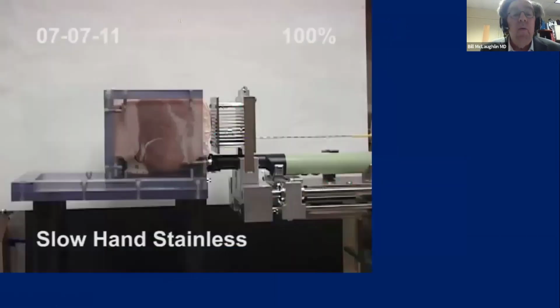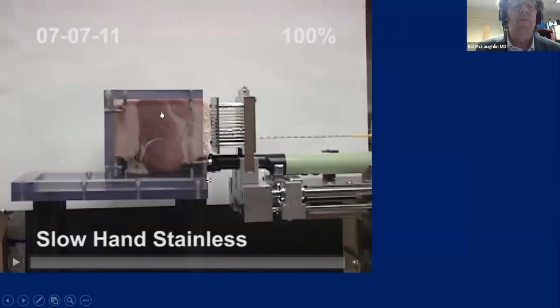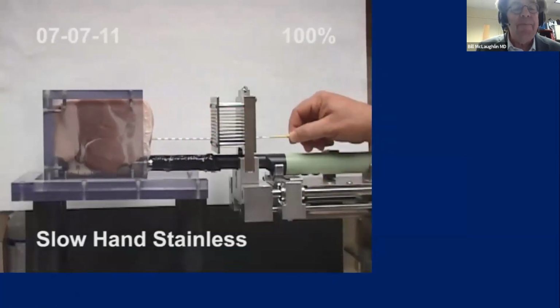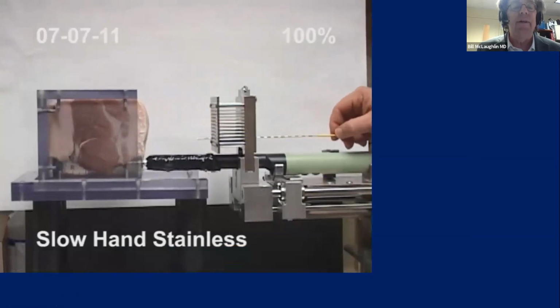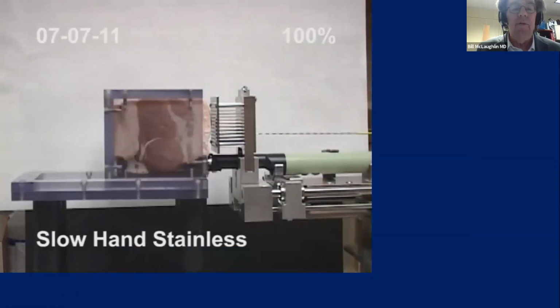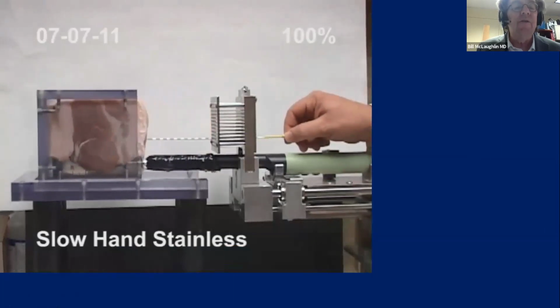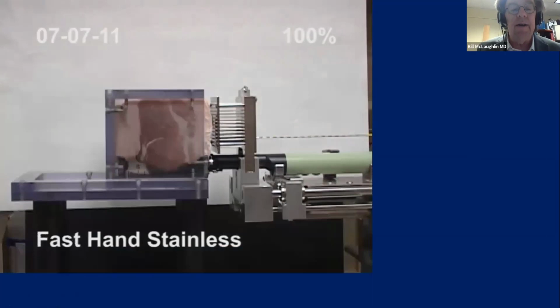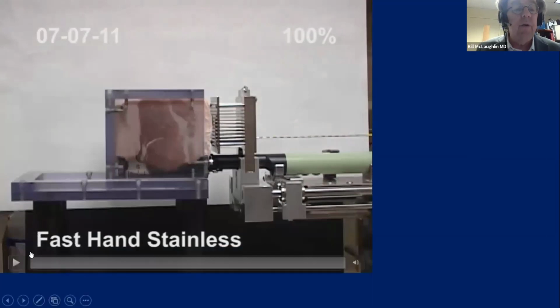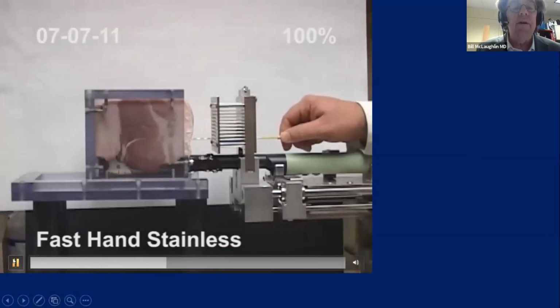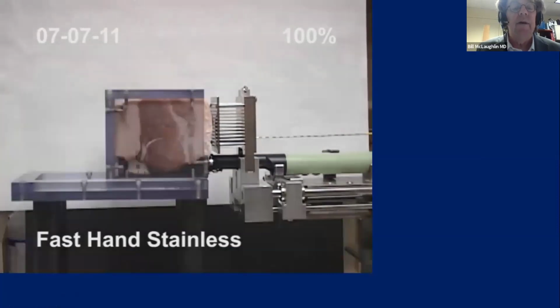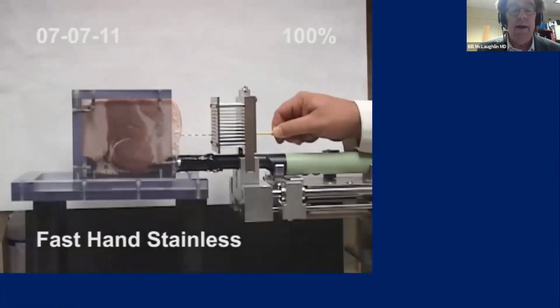And so what we did years ago, and we're going to reapply, is we created a phantom. This is an 8-pound block, tissue equivalent, used to demonstrate the fact that the needle goes a certain distance and then you get this lollipop effect. Now, if I go faster, I can do a little better. But still, even at the fastest I do, I'm still getting that needle binding.